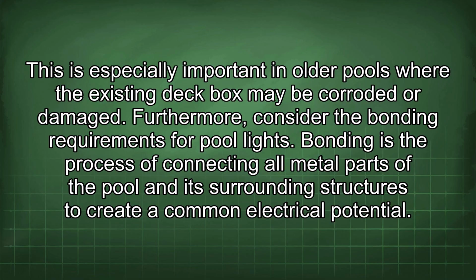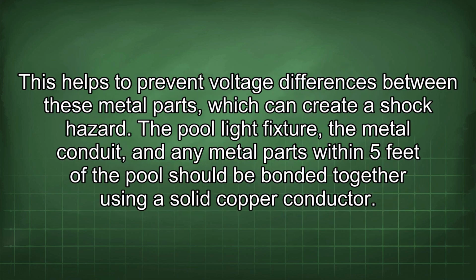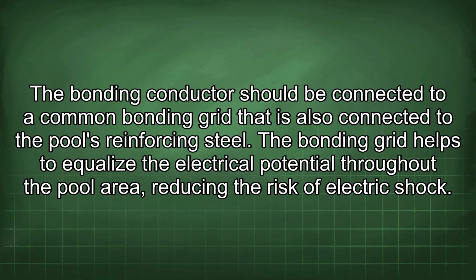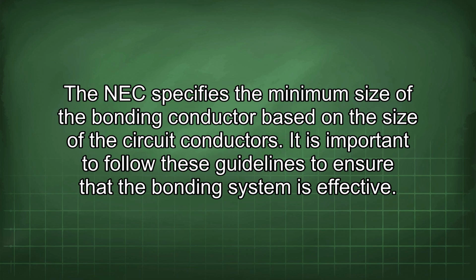Furthermore, consider the bonding requirements for pool lights. Bonding is the process of connecting all metal parts of the pool and its surrounding structures to create a common electrical potential. This helps to prevent voltage differences between these metal parts, which can create a shock hazard. The pool light fixture, the metal conduit, and any metal parts within 5 feet of the pool should be bonded together using a solid copper conductor. The bonding conductors should be connected to a common bonding grid that is also connected to the pool's reinforcing steel. The bonding grid helps to equalize the electrical potential throughout the pool area, reducing the risk of electric shock. The NEC specifies the minimum size of the bonding conductor based on the size of the circuit conductors. It is important to follow these guidelines to ensure that the bonding system is effective.